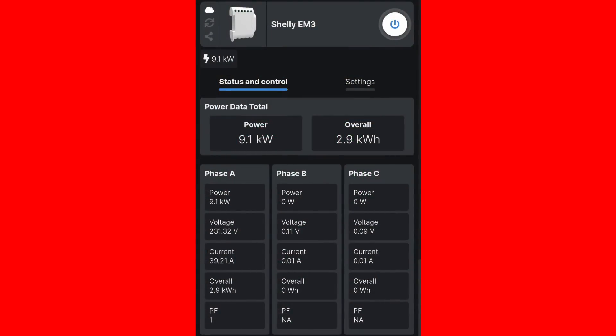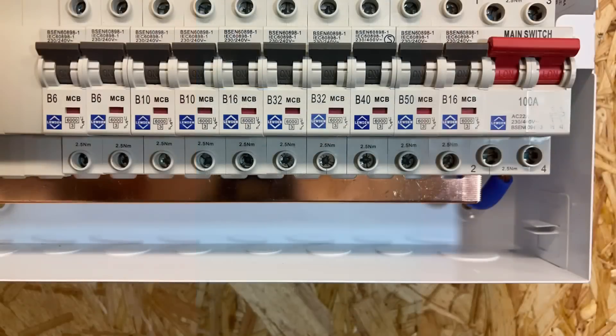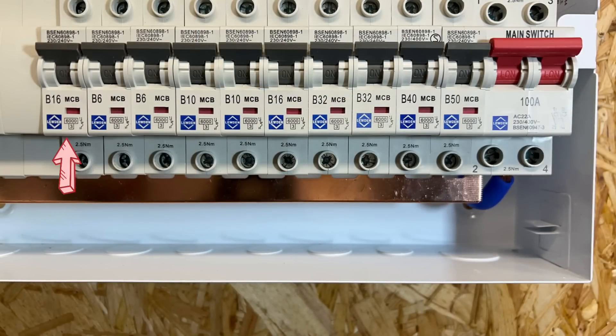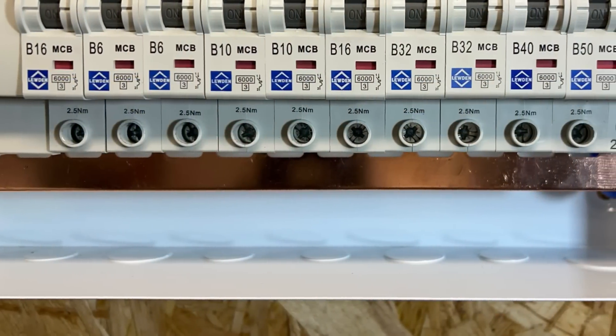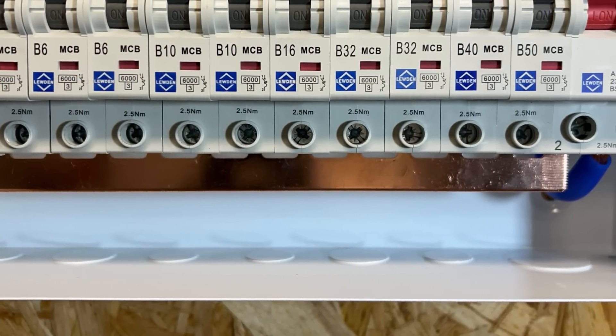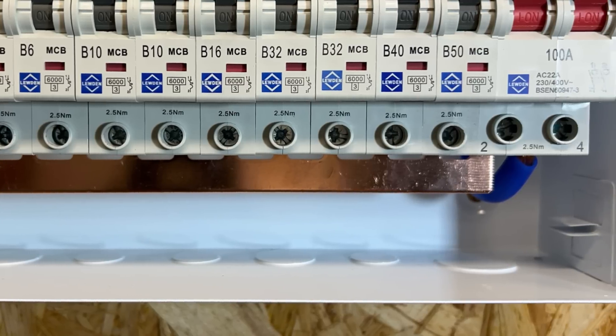Now there are debates to be had here, as there always are with developing technologies and the regulations that respond to them. We could say that the installation is likely to never draw that amount of current, especially taking into account the information on maximum demand, or that if we place the protective device for the PV panels at the other end of the busbar so that no one part of it ever conducted the full 116 amps. But that regulation really is pretty clear that you cannot have a PV system feeding a consumer unit rated at 100 amps if the incoming supply is fused at 100 amps. Not only are you becoming non-compliant with the regs, but you're also going against the manufacturer's instructions and using the equipment for a purpose it wasn't designed to cope with. If the installation started drawing that much current, the heating effect through the busbar will still be affected by the current in the different parts, even if it's not all flowing through the same section.